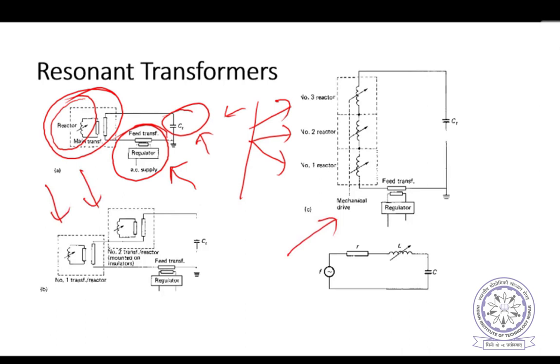Here, instead of changing using a transformer, a mechanical drive is used, which will change the core or air gap in the core and adjust the reactance value. The difference is only in the mechanism of how we are changing the reactance of the inductor to achieve the resonance. But this one is transformer action. This is the better one in my opinion.